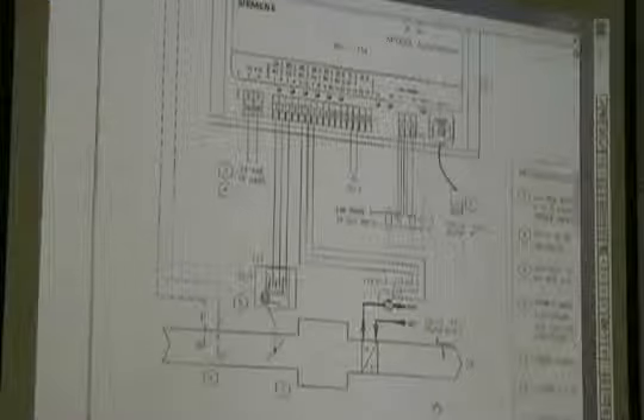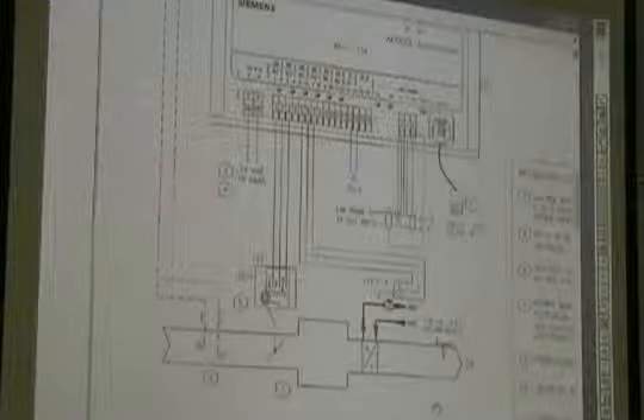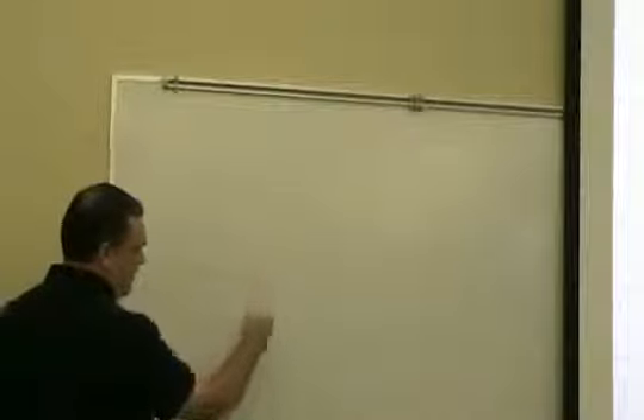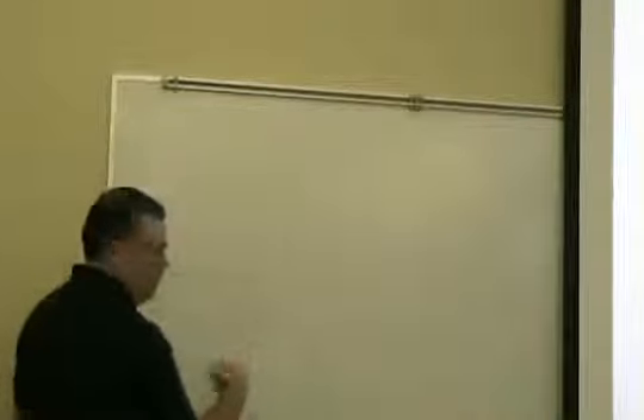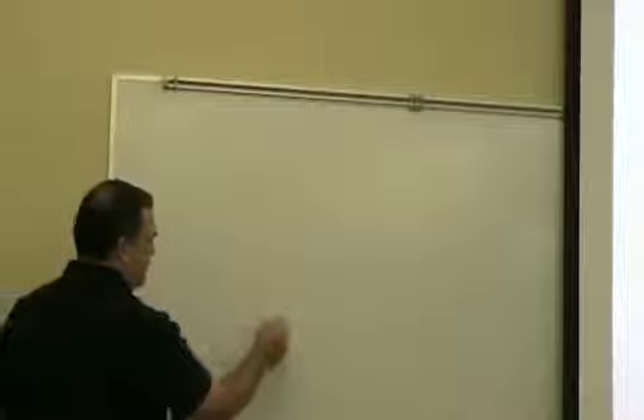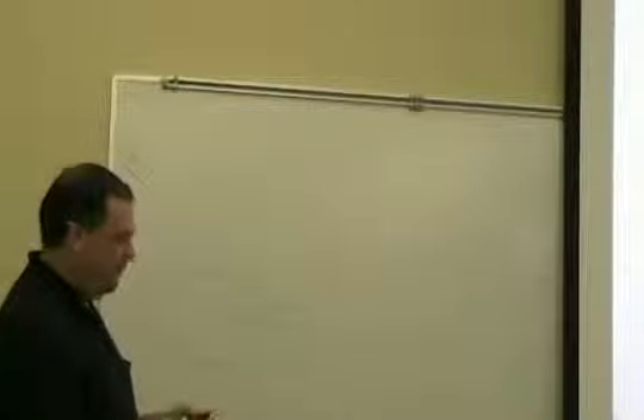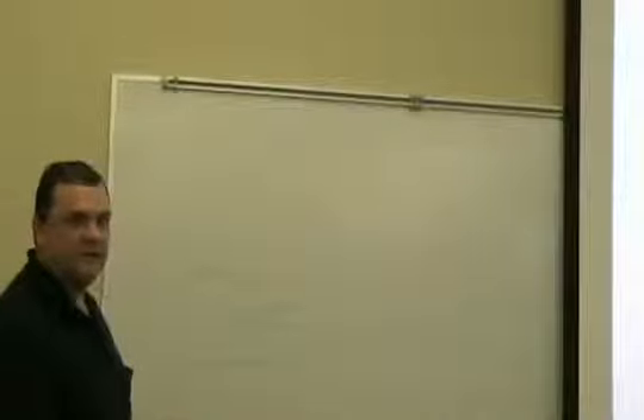The last one you hooked up. How much does it take? How much rotation does it take to open or close that damper fully? Depends. Some of them 45, some of them 90. Yeah, there's about 3 different scenarios. Some of them, the damper is in there, straight up and down, it's fully closed. Straight across, it's fully open. So that'd be a 90-degree rotation. Okay, that fits perfectly with our actuator that does 90 degrees.